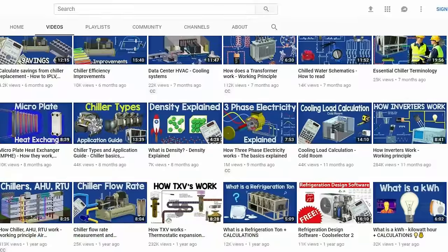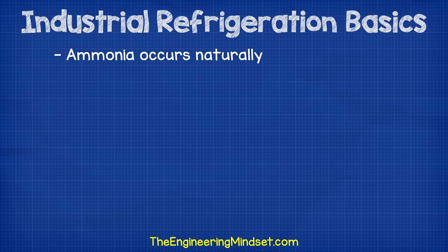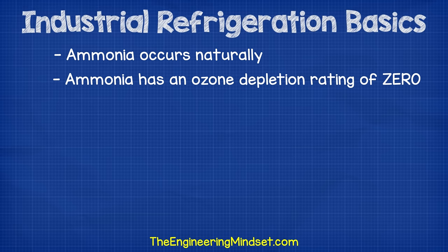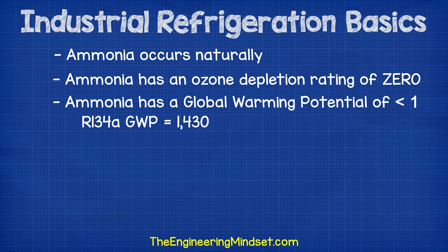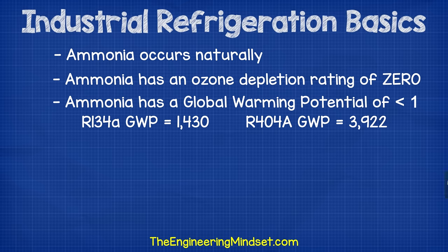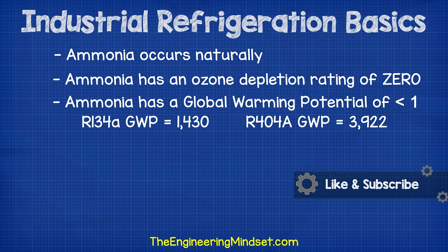I just want to very briefly touch on why we use ammonia as a refrigerant. Ammonia occurs naturally in the environment and is available in abundant amounts. It has an ozone depletion rating of zero and a global warming potential of less than one. If we compare that to other common refrigerants, such as R134A, which has a GWP of 1,430, and R404A which has a GWP of 3,922, you can see why ammonia is very beneficial to use.